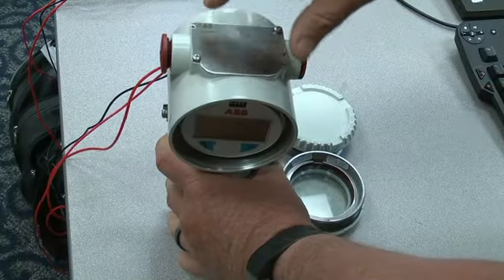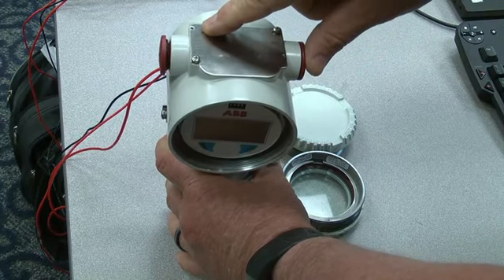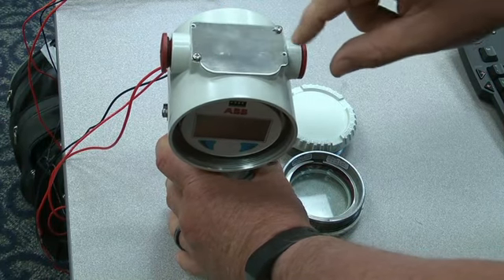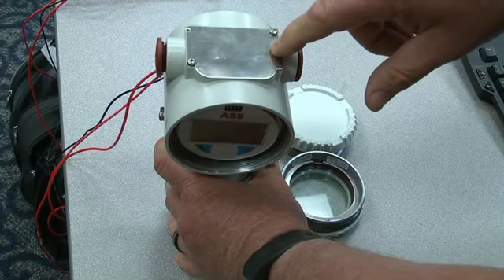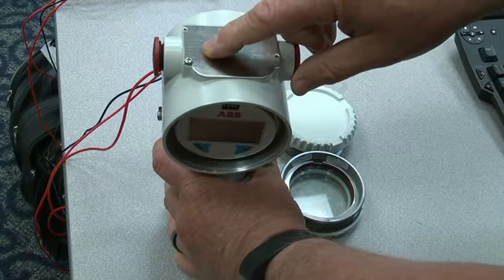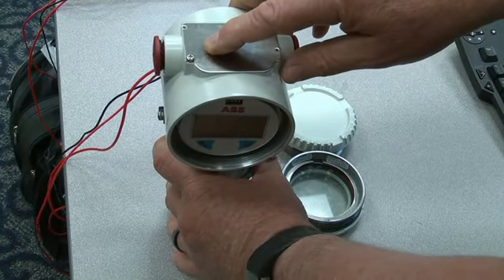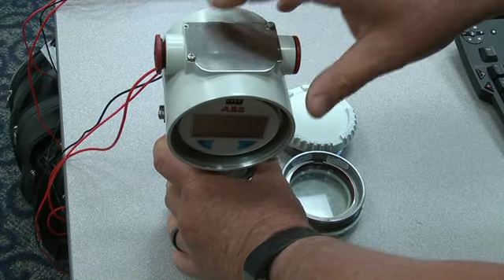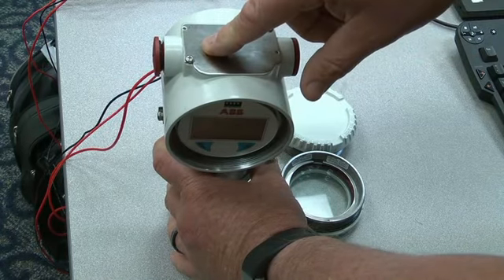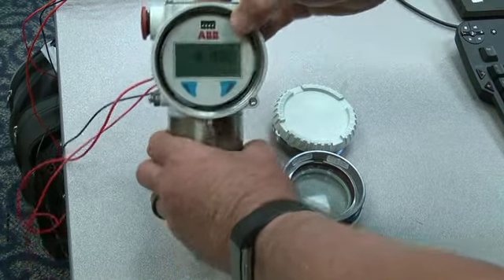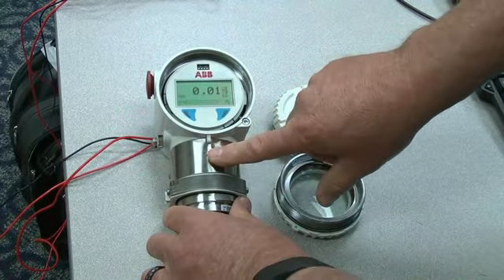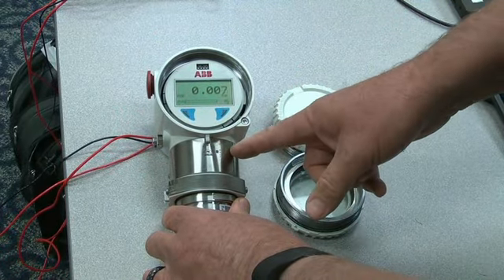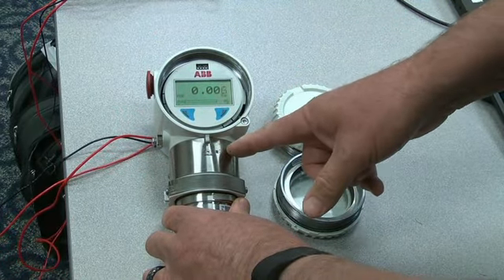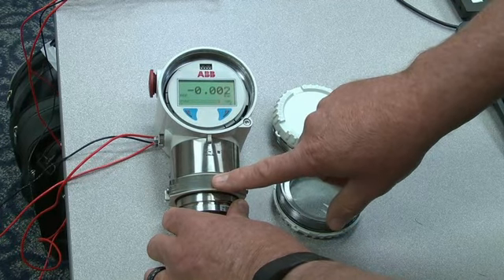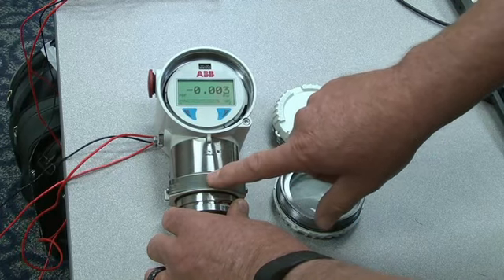On the 266, the top plate is the indicator for our product code. It also is the indicator for the output voltage, and it also is the indicator for the input voltage. This is an 8 to 30 volt with a 1 to 5 volt output. We want to make sure that we don't exceed that 30 volt maximum. The center plate here is the indicator for the explosion proof housing for the codes. The lower plate is going to give us our range. This is a 0 to 1500.